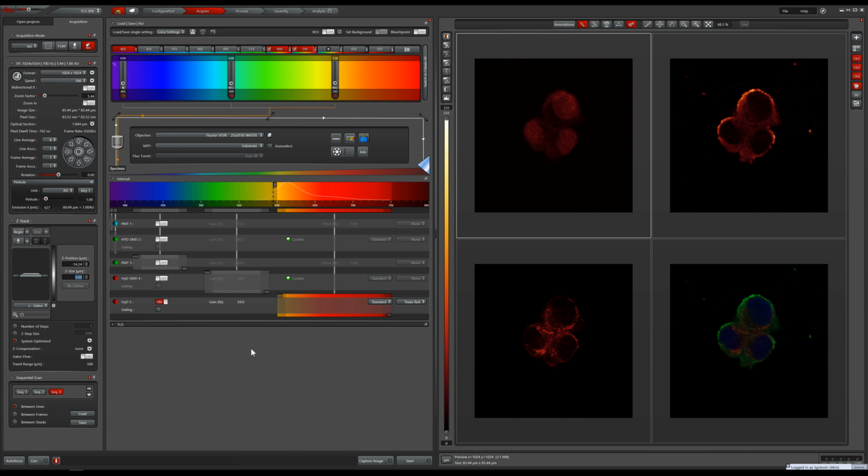Now, let us find a fresh area and the right focal plane to acquire another Z-Stack. The system-optimized setting would be 600 nanometers thick slices, but we change this to 400 nanometers. Although the system knows its own optics best and can calculate Nyquist for you, Leica only gives you the best option for one channel effectively. With 400 nanometer sections, we sample at a higher rate than the system-optimized setting, as slightly oversampling will help us if we wanted to deconvolve those images later while avoiding potential undersampling in our channel of interest. Although we increased the sampling rate by reducing the step size, the time we spend scanning was not overly inflated and well worth the gain.